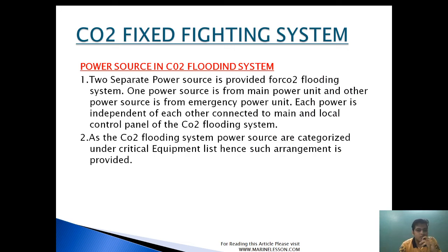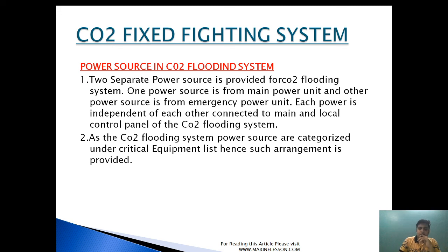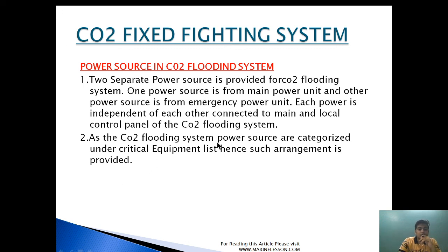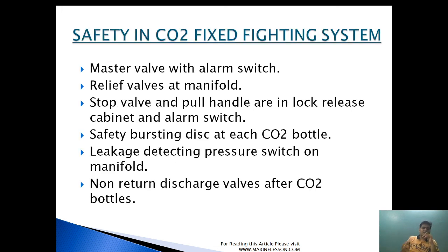Two separate power sources are provided for the CO2 flooding system. One power source is from the main power unit and the other is from the emergency power unit. Each power source is independent from the other, connected to the main and local control panel of the CO2 flooding system. Since the CO2 system is part of the fire control system and an essential service, it is provided with emergency supply. The CO2 system power sources are categorized under critical equipment, hence this arrangement is provided.